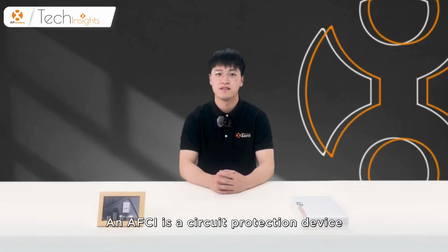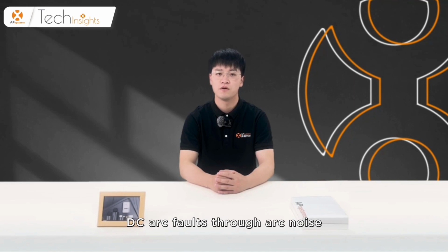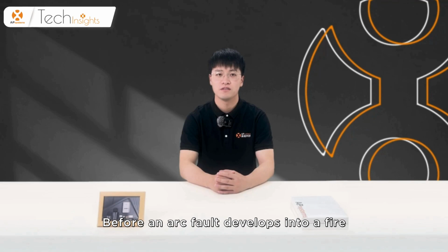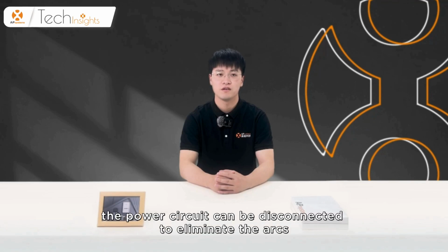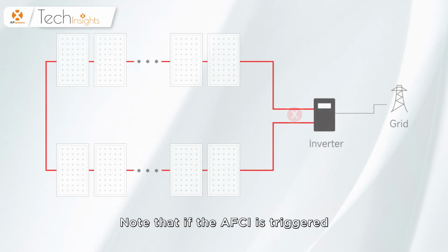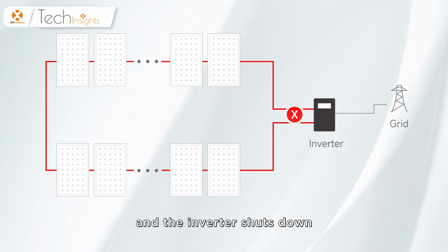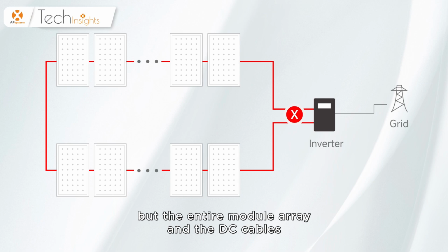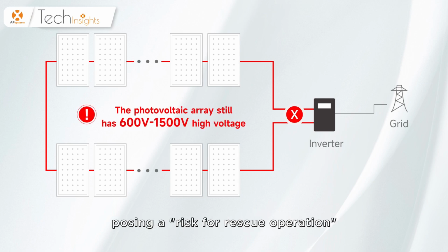An AFCI is a circuit protection device that identifies characteristic signals of DC arc faults through arc noise. Before an arc fault develops into a fire or a short circuit occurs, the power circuit can be disconnected to eliminate the arcs. Note that if the AFCI is triggered and the inverter shuts down, the DC terminal can be disconnected from the AC terminal, but the entire module array and the DC cables remain in the high voltage state, posing a risk for rescue operation.